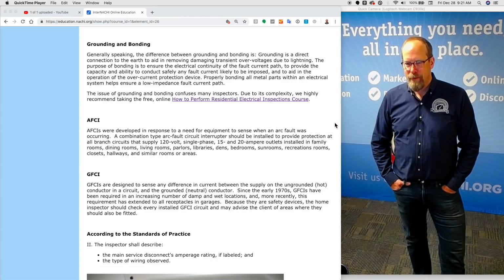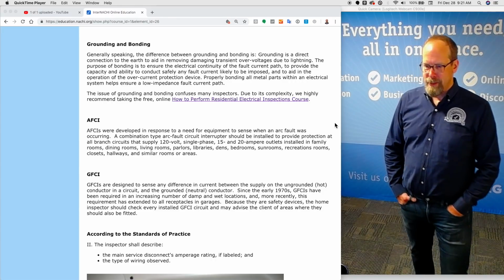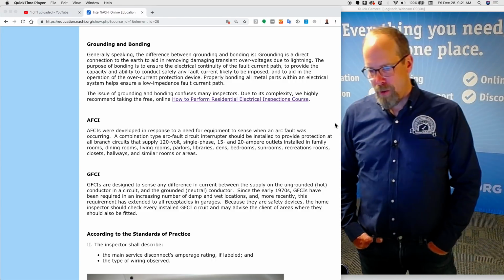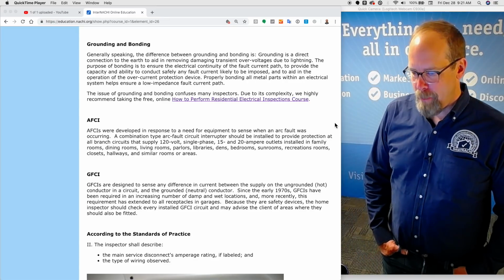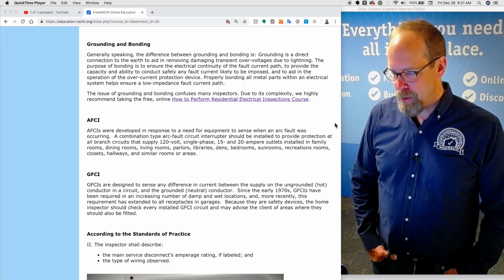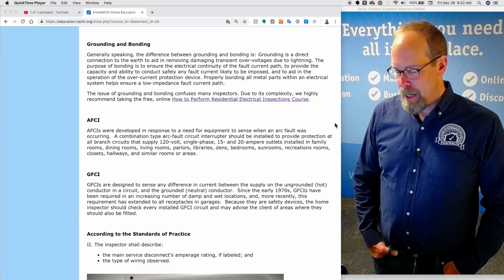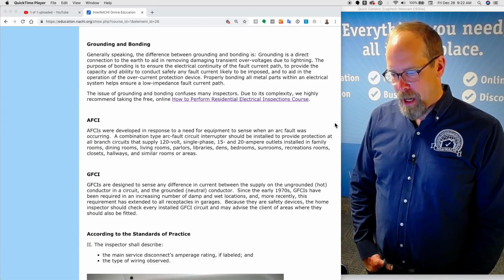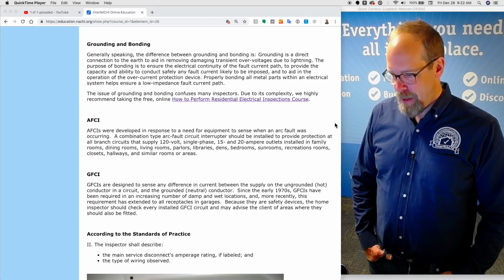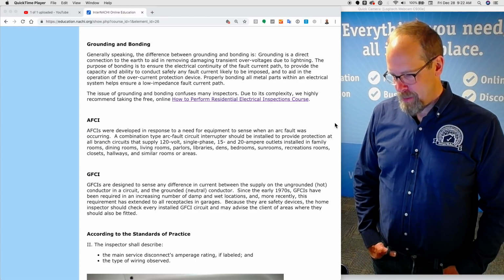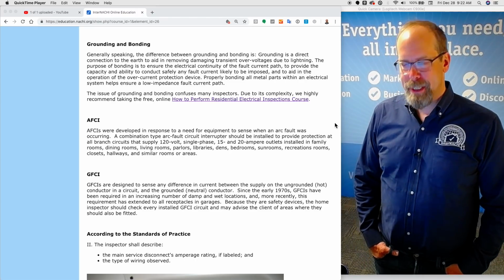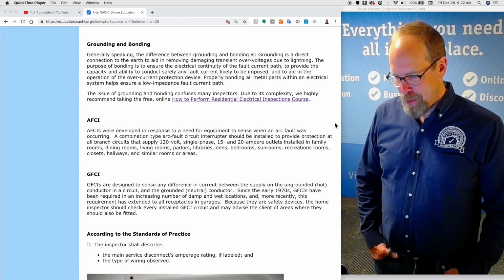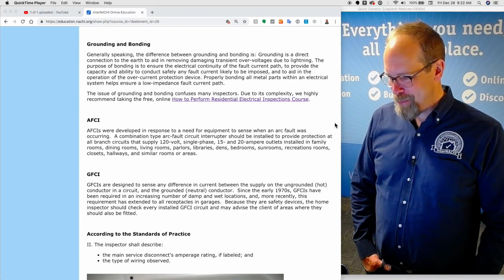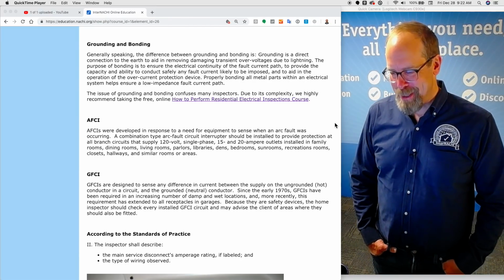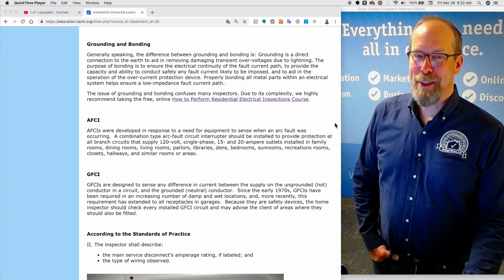AFCIs. They were developed in response to a need for equipment to sense when an arc fault was occurring. A combination type arc fault circuit interrupter should be installed to protect all branch circuits that supply 120 volt single phase 15 and 20 amp outlets installed in family rooms, dining rooms, living rooms, parlors, libraries, dens, bedrooms, sunrooms, recreation rooms, closets, hallways, and similar rooms or areas. There's a lot of rooms.